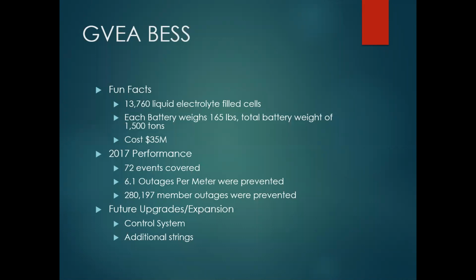One question I had is, how long do those batteries last? Do they have to be replaced periodically? They have what they say is a 20 to 30 year lifespan, right? They were put in in 2003. The battery manufacturer's representative comes up once a year in the springtime, normally around the beginning of May, and there are 4 strings, so we switch out one string at a time. We go through and check fluid levels on all of them. If there are ones they suspect are problems, they'll check voltage and resistance on them. So we're constantly looking at it.